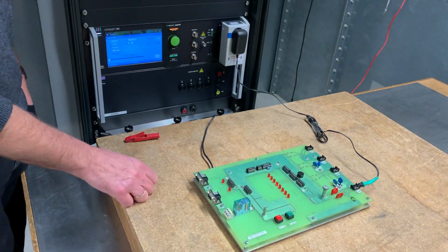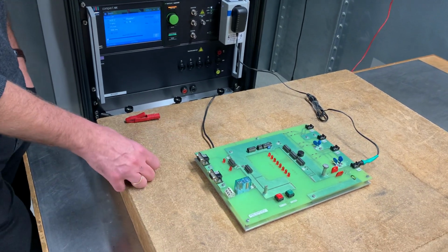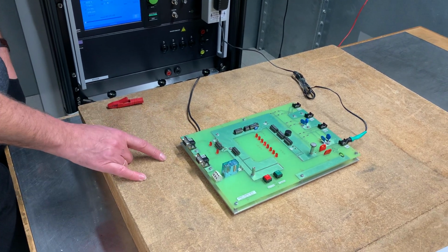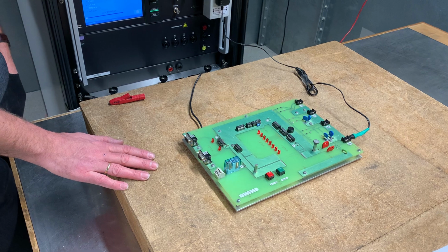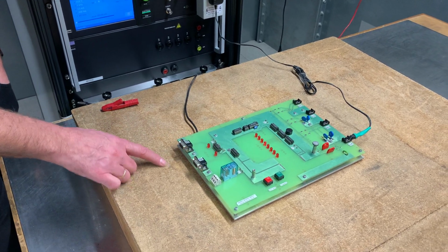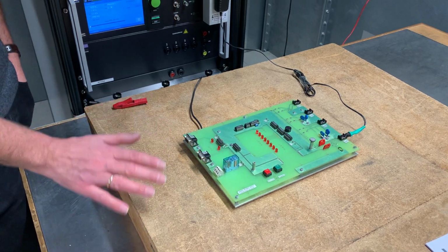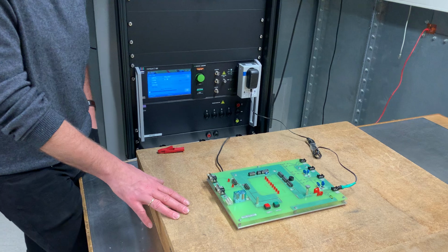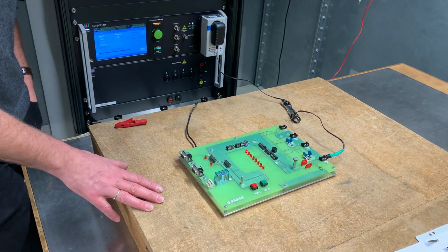Strictly you could say maybe this is a criterion B, which is passed. But what is the effect when the relay is switching in real practice? Maybe that is an emergency switch or whatever. We'll switch the whole electricity off. So it's a big question if this is a performance criterion B or not.